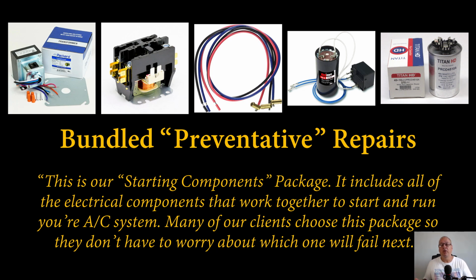What about the capacitor for the compressor motor? And what if we go with more robust components — upgrading the transformer to one that's fused or has a built-in breaker? Could we bundle something like this under a packaged name and say, we can take care of this contactor today, but these other components are showing signs of wear and tear — what if we do what we call our starting components upgrade, where we replace all the components in the startup circuitry so the compressor and fan motor get every benefit possible?